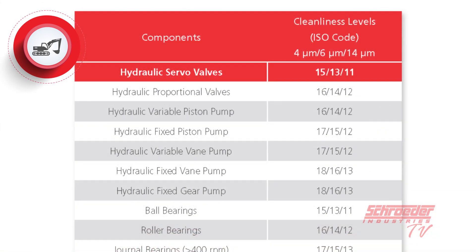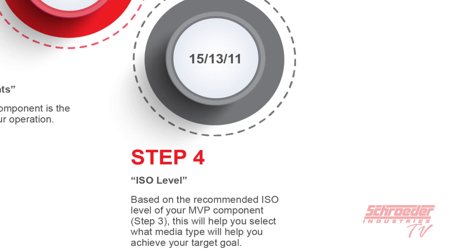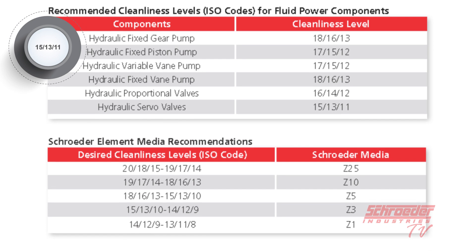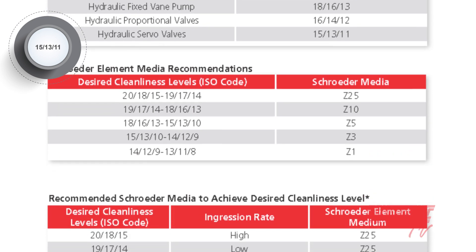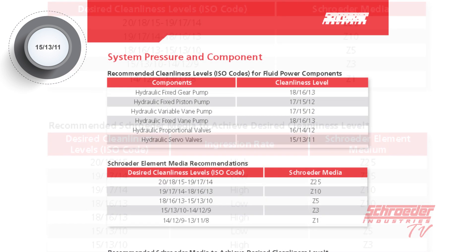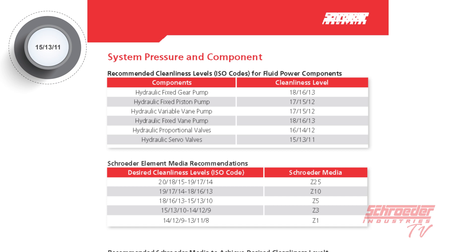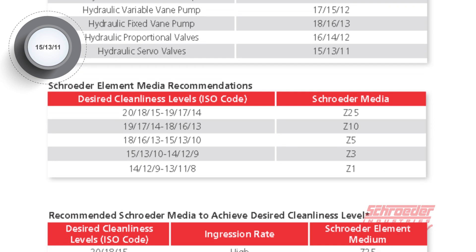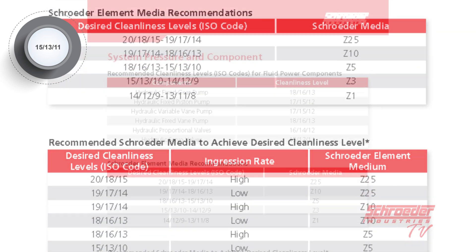The component OEMs will also list ISO code cleanliness recommendations in their own product catalogs if you are looking for a more precise code for your system. Step four is to use the ISO code you found in step three and match it to a micron rating. Each ISO code has a specific micron-rated filter element you should use to best capture and retain the size of contamination most prevalent in your system. Using this chart will guide you to choose the correct micron rating. If you're between ratings, remember you can always go to the lower ISO code.